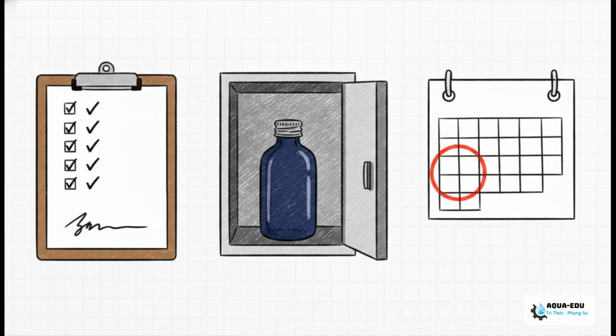Finally, it's paperwork time. Fill out every single line of your calibration form. I mean everything. Record the lot numbers, the theoretical millivolts, the offset adjustment, and the handheld verification numbers. Check that pass box and sign your name. Make sure your standard solutions are capped super tight and stored away from direct light. Then, set a reminder for your next calibration. Usually that's in 1 to 3 months, keeping in mind that these electrodes generally need a full replacement every 12 to 24 months, depending on how tough your plant's conditions are.